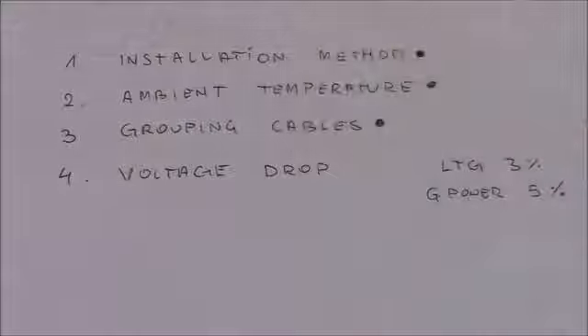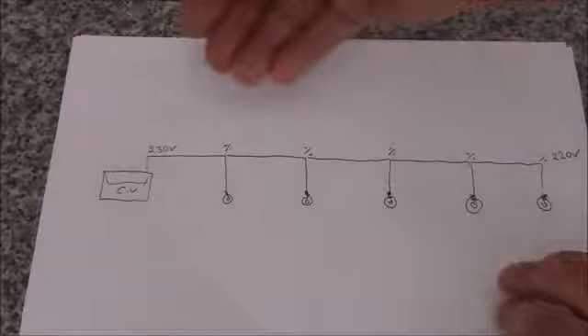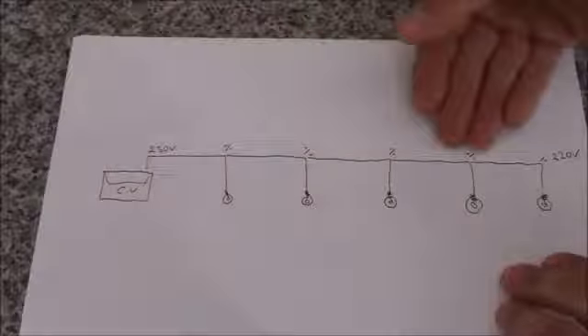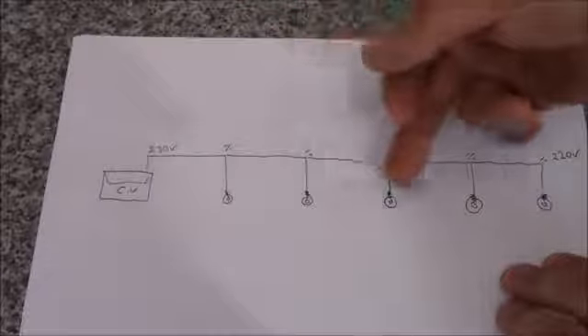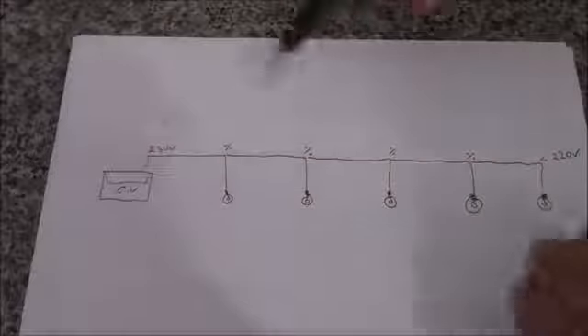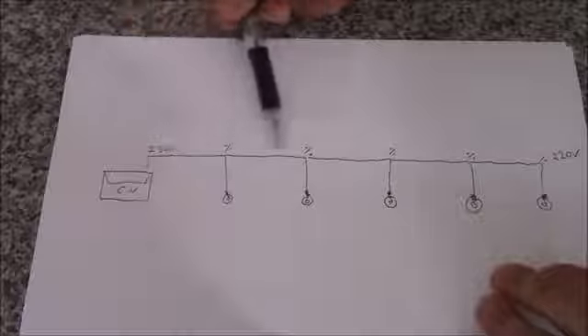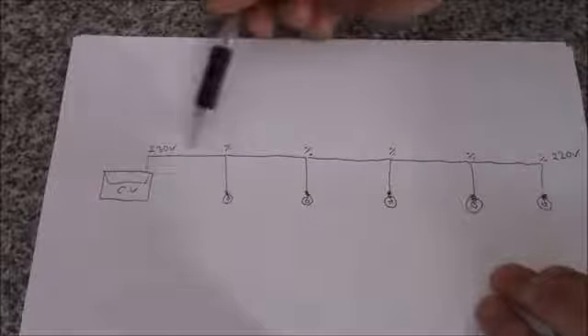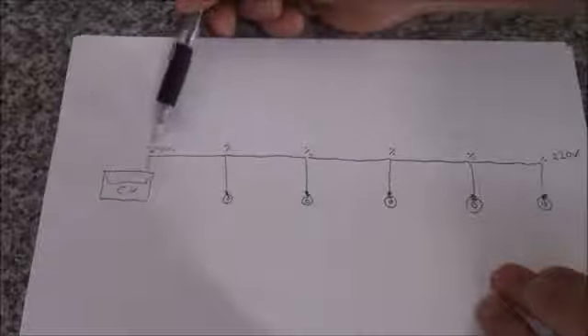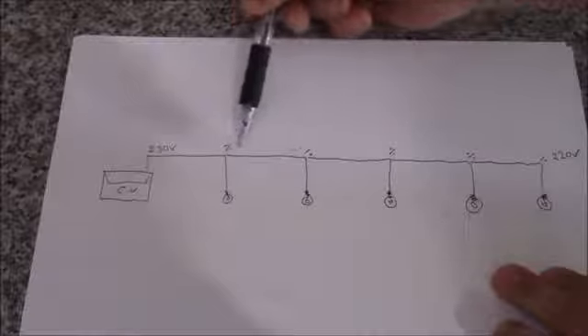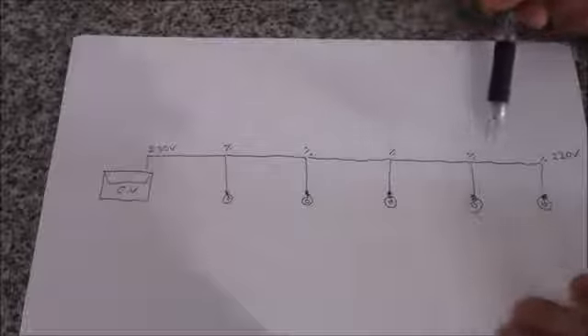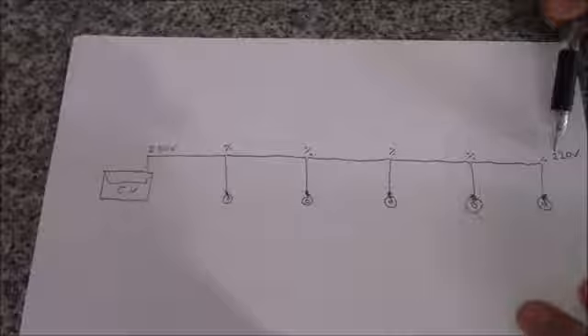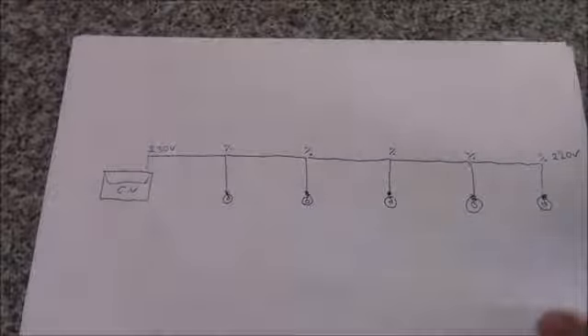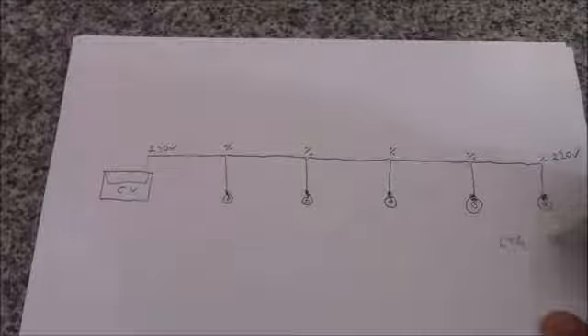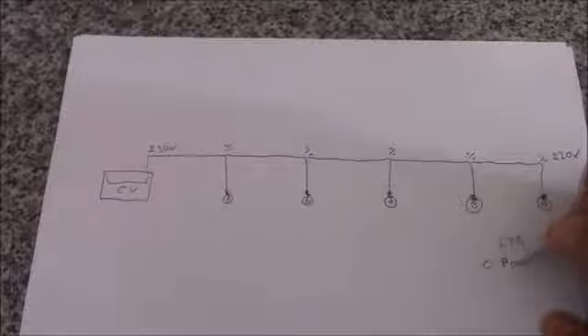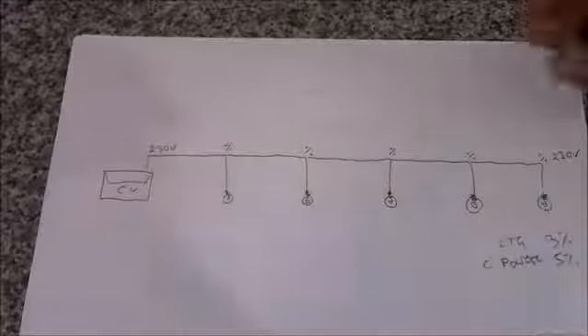And the voltage drop. The voltage drop or voltage loss occurs in every circuit, and it depends on the length of the cable on the circuit, and obviously on the items or bulbs that are connected to the circuit. So here we've got a typical lighting circuit, consumer unit, let's say 5 rooms, 5 light fittings with a bulb. At every point there's some voltage loss. At the beginning we've got 230 volts. There's voltage loss in every meter of the cable. So at the end it might appear that we've got only 220 volts. In the UK the allowable voltage drop for lighting circuits is 3%, and for general power it is 5%. So you need to consider this as well when choosing the cable.